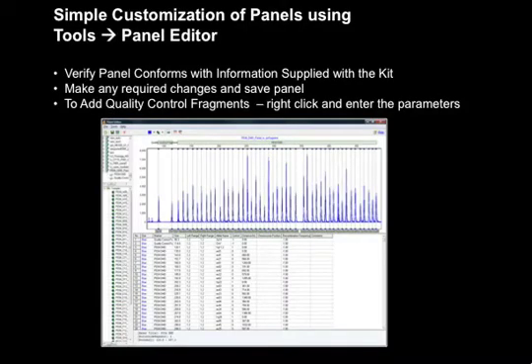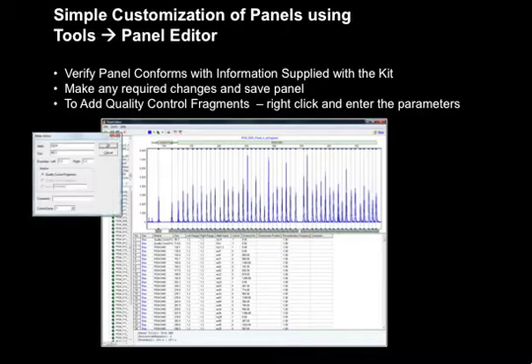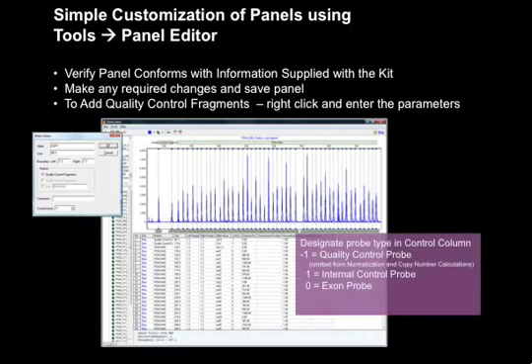MLPA kits are often revised and customized. The most up-to-date information comes from the manufacturer of the kit or chemistry. Use the panel editor to verify that the panel conforms with the information supplied with the kit. Minor changes can easily be added to the panel editor by right-click and add, edit, or delete alleles. The control column of the table is used to designate the probe type. A negative 1 in the control column indicates a quality control probe, which is excluded from normalization and copy number calculations. 1 is used for internal control probes and 0 for exon probes.